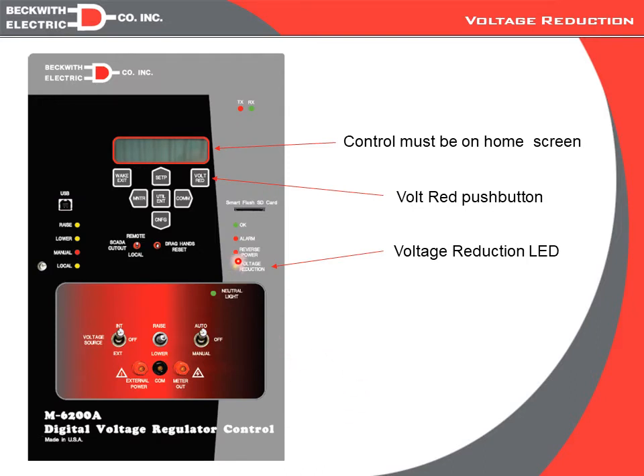So looking at the control, there is the voltage reduction LED, and there is the voltage reduction push button. Now, to access voltage reduction locally, we would have to be on the main screen on the HMI. If we're not on the main screen, we would hit the exit button until we got back to the main screen. Once on the main screen, if we hit the voltage reduction button, we will be prompted as to what stage we want to enter, and then if we hit the enter button after selecting a stage, we would see the voltage reduction light go on. We would be in reduction at that percentage, and it would stay on until we left the reduction.